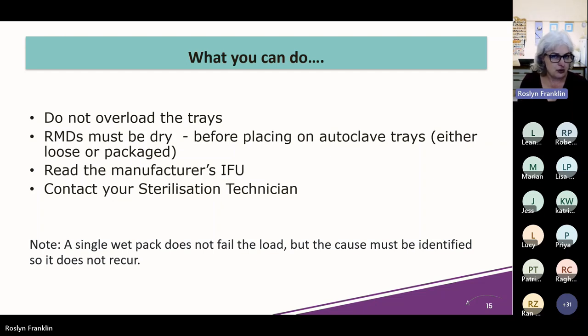But if you have two or more wet packs, I wouldn't release it. You need to investigate why, and those instruments, the load deemed failed, need to go back through that cleaning and packaging system again.